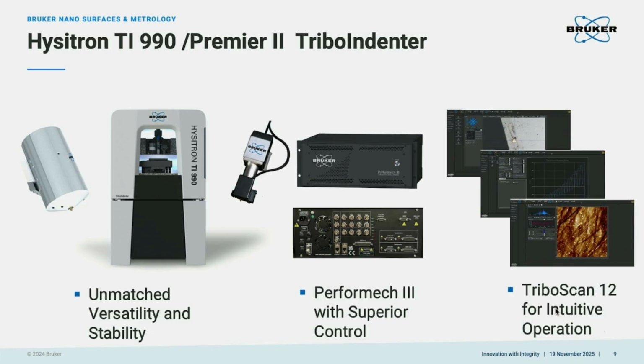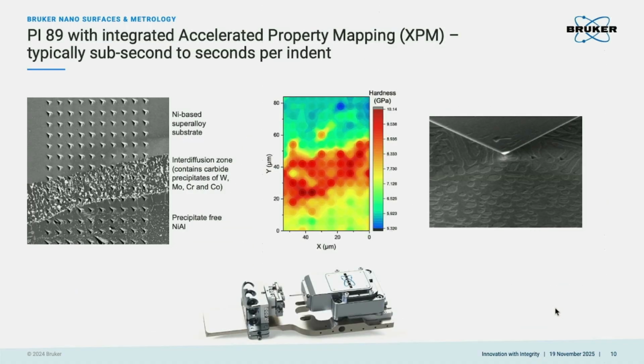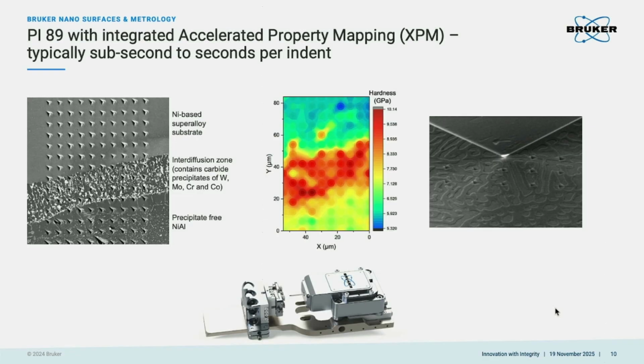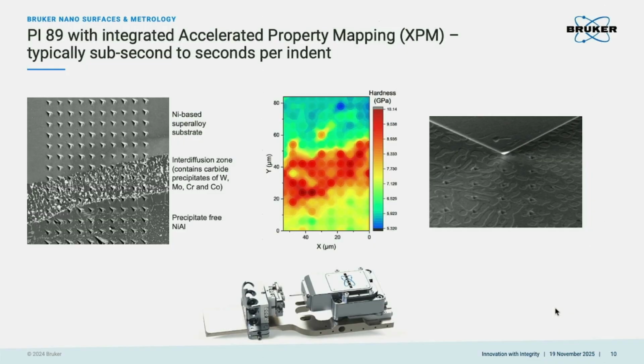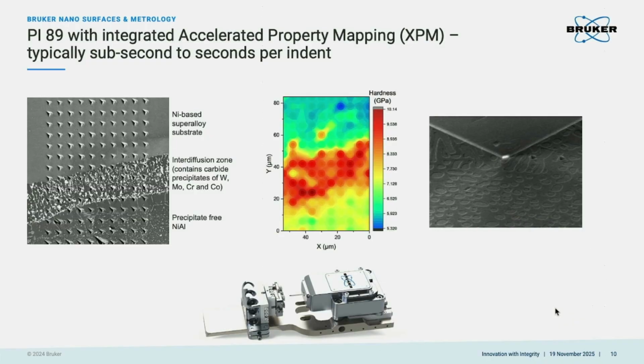Yeah, of course, we have the new software and controller, and also the high-load transducer, which allow us to do high-speed mapping. We can also perform high-speed mapping in the SEM, right? This is a video of the high-speed mapping, at real speed. It's almost 1 second per indent inside the SEM. You can see a very clear image of the different interfaces and phases of the material, and the mechanical properties after the high-speed mapping.